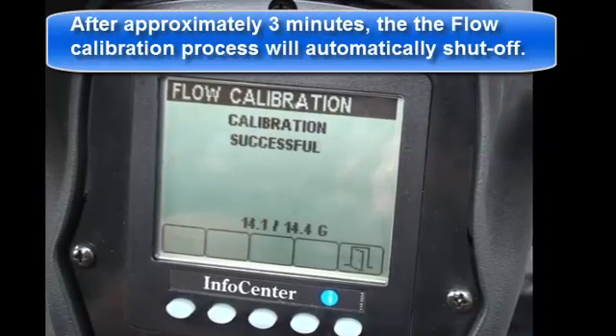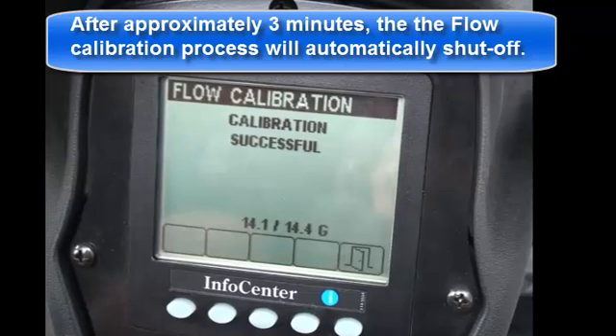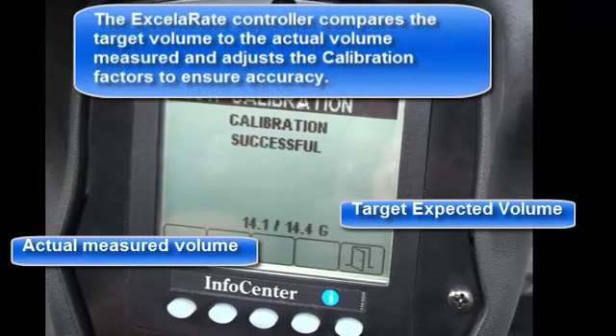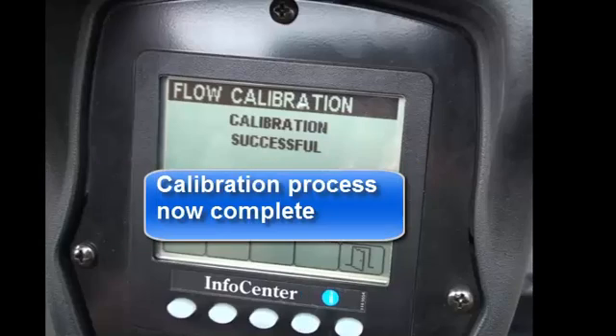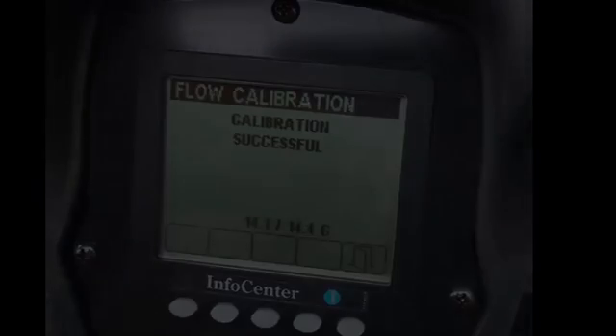After approximately 3 minutes, the flow calibration process will automatically shut off. The controller compares the target volume to the actual volume measured and adjusts the calibration factors to ensure accuracy. Calibration is successful — press the right arrow button to exit and save calibration. The calibration process is now complete.